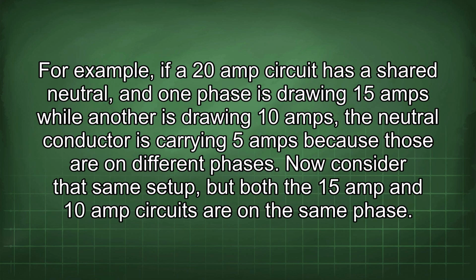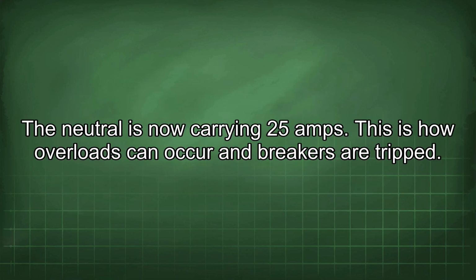For example, if a 20 amp circuit has a shared neutral, and one phase is drawing 15 amps while another is drawing 10 amps, the neutral conductor is carrying 5 amps because those are on different phases. Now consider that same setup, but both the 15 amp and 10 amp circuits are on the same phase. The neutral is now carrying 25 amps. This is how overloads can occur and breakers are tripped.